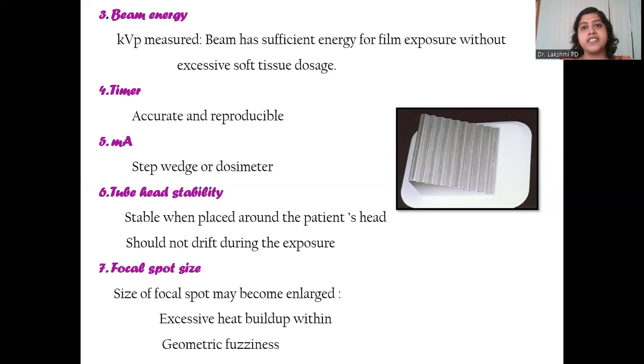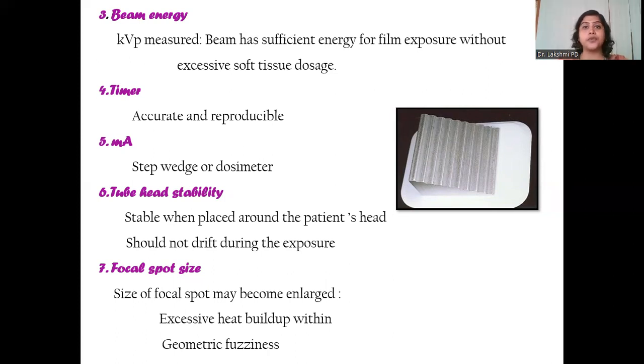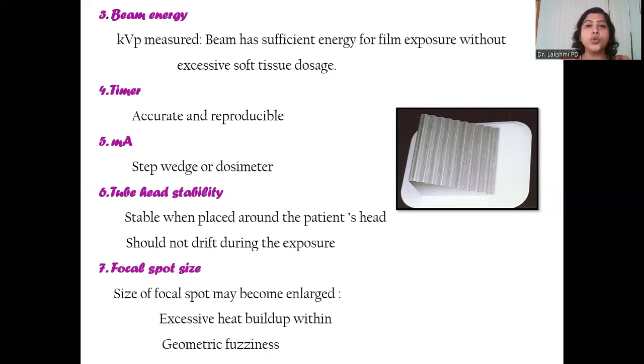The seventh check is your focal spot size. On excessive use, excess heat builds up within your x-ray machine that can lead to enlargement of the focal spot size — something we cannot detect ourselves as it is all internal to the machine. An enlarged focal spot ultimately leads to geometric fuzziness, meaning you lose image sharpness, edge sharpness, and resolution. These are the seven yearly tasks recommended to be done by a dental service company or health physicist at the end of every year.